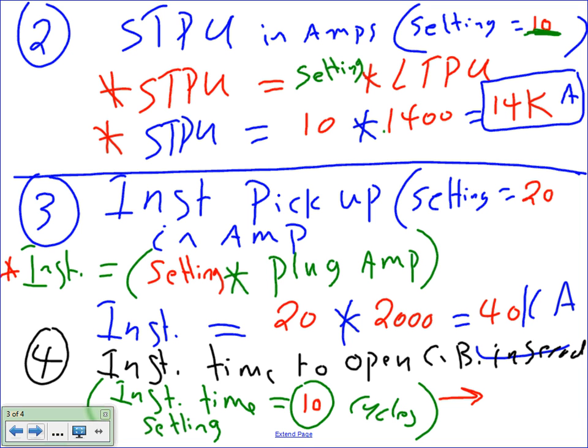The last thing I want you guys to do in this example is instantaneous time. I didn't ask about the long time delay and short time delay because these are a piece of cake. The delay is always in seconds. So what are you going to calculate? Either you put 0.3 seconds, 1 second, 2 seconds. There's nothing to calculate. The long time pickup, short time pickup, and instantaneous are the ones that you need to do some math on. And the SKM software that we use goes through the whole calculation for you.